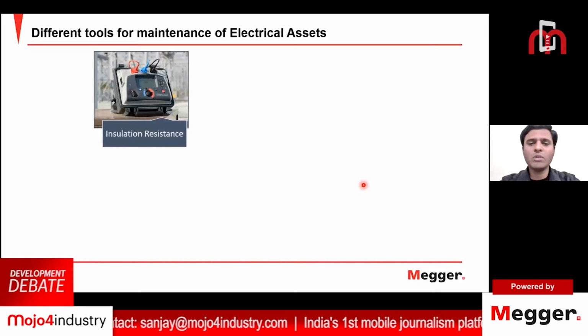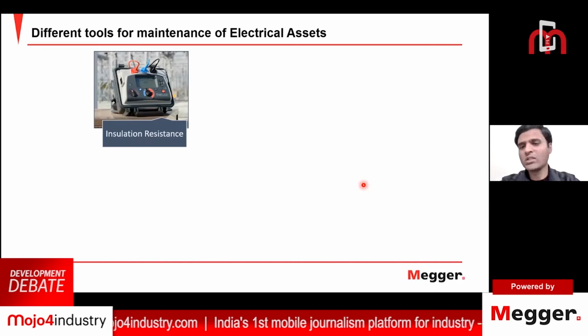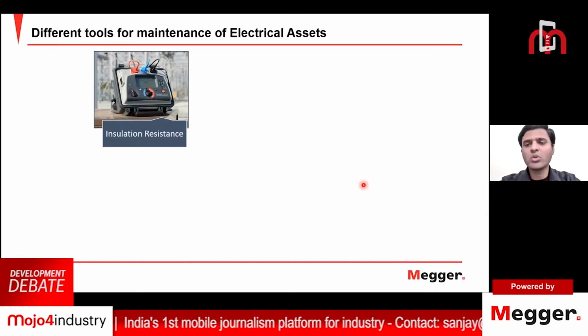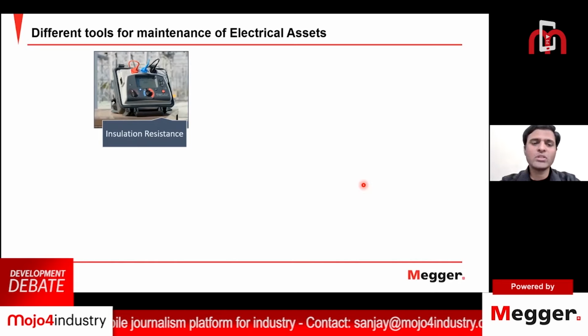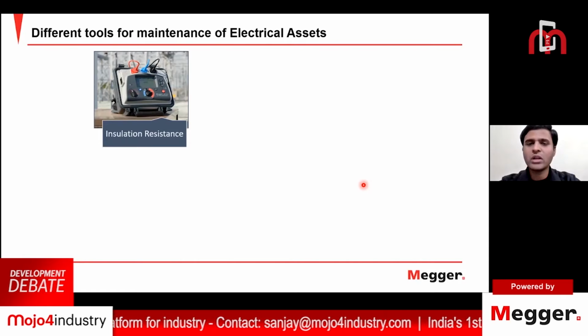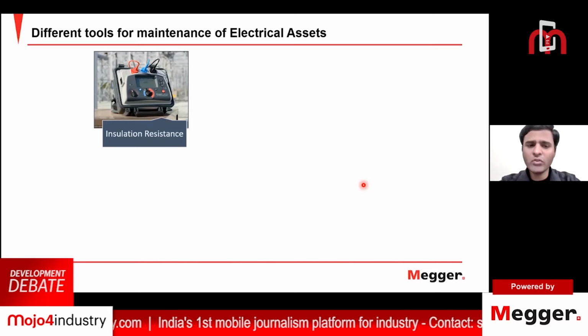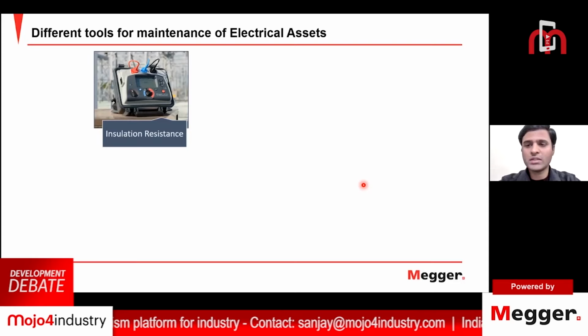There are different tools available in the industry to carry out maintenance work from reactive to predictive. The basic test we conventionally use is the insulation resistance test. It is carried out in offline condition: the electrical asset is shut down, a DC voltage is injected into the DUT, and the IR value is measured. However, this helps you identify the cause of failure only at a later stage. If your electrical asset has already failed, the IR value will indicate deterioration. If it has not failed, the IR value will be higher and indicate the asset is healthy, but it will not help you predict any failures in the coming time period.